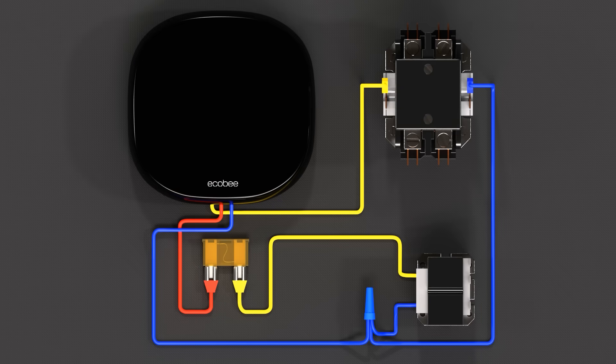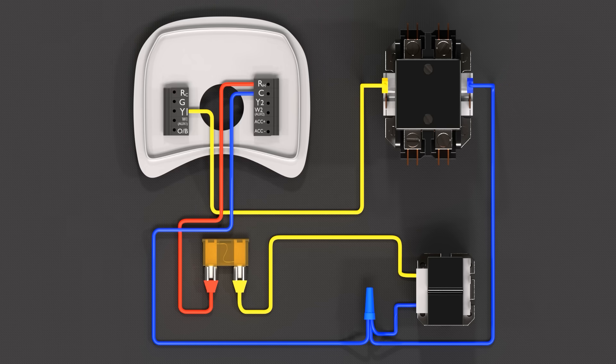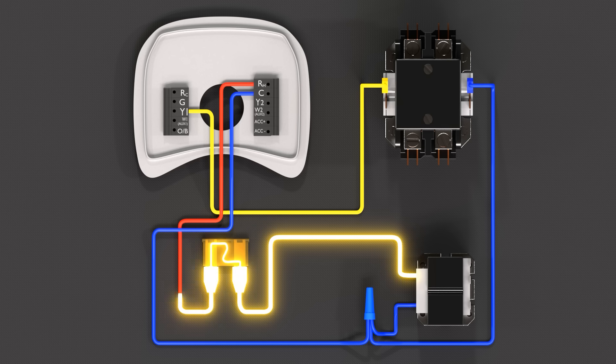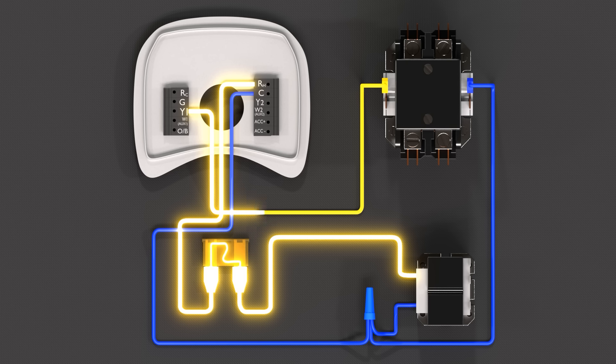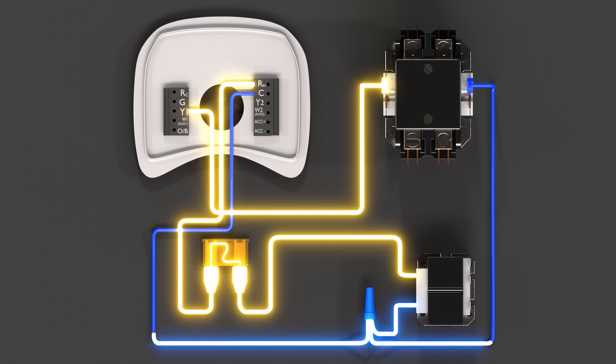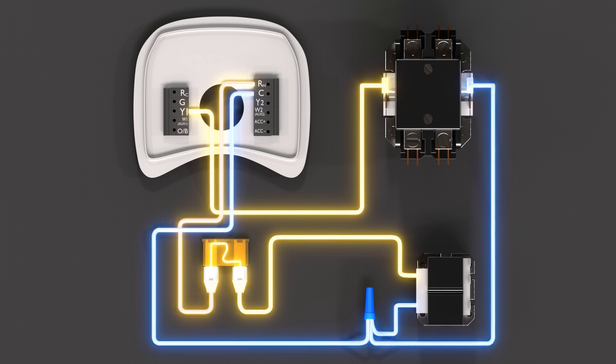Next, let's show a simplified version of the AC electrical circuit. Rather than being a heat pump, we're only showing the low voltage side of what energizes our compressor contactor for simplicity. Our 24-volt power comes out of our transformer, travels through our fuse, then up to power the thermostat. When calling for cooling, the thermostat energizes the Y terminal, which then can bring on our contactor by energizing the electromagnetic contactor coil. It then needs to travel back to the other side of the transformer common to complete the circuit.